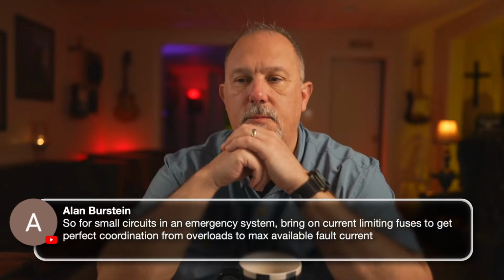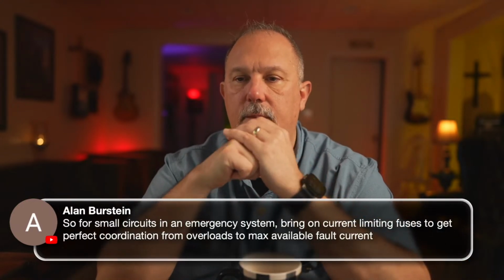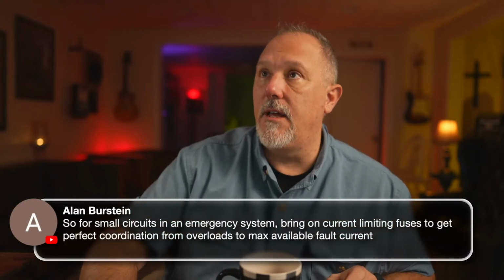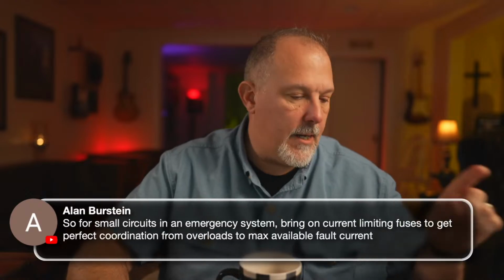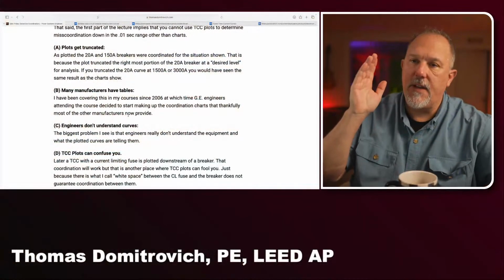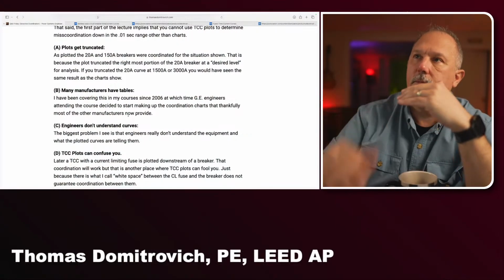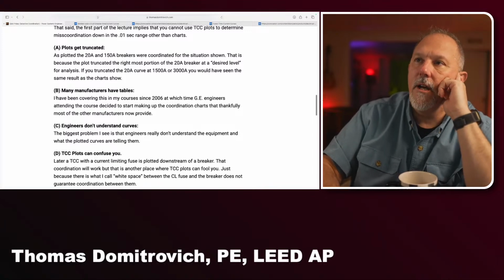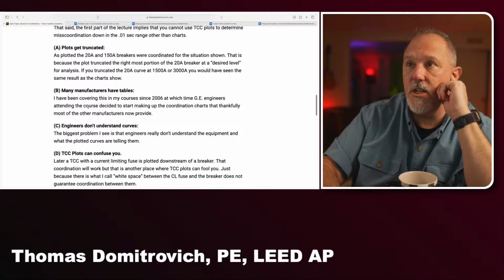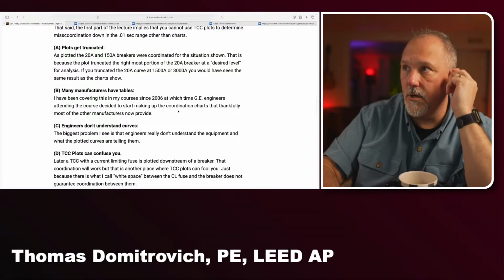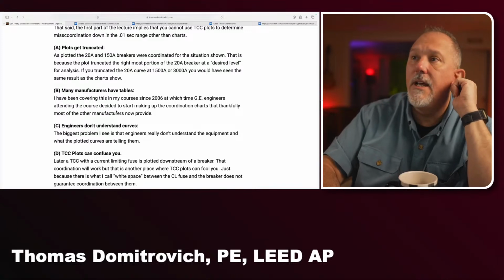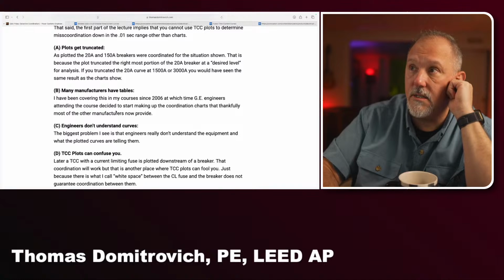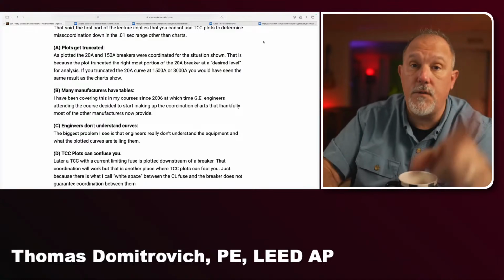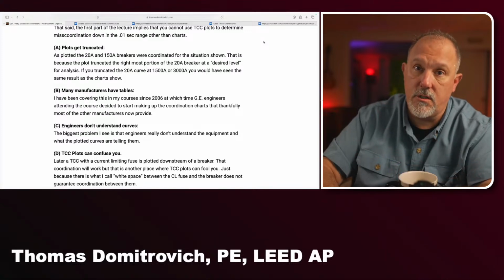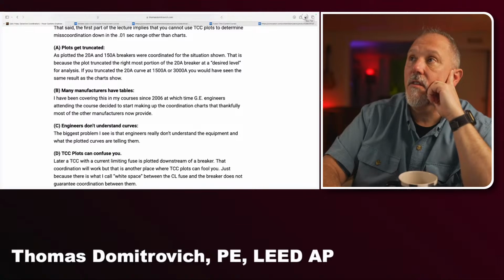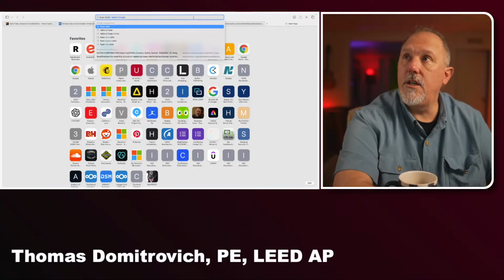So for small circuits in an emergency system, bring on current limiting fuses to get perfect. So this is the other part of the question. The tables. So if I go back to the second item, he's been covering this in his courses since 2006, at which time GE engineers attended the course, decided to start making up the coordination charts that thankfully most of the other manufacturers now provide. I would argue well before 2006, we have had selective coordination tables for fuses. Fuses were the first ones to introduce this, and that was a long time ago. The fuse ratio tables.